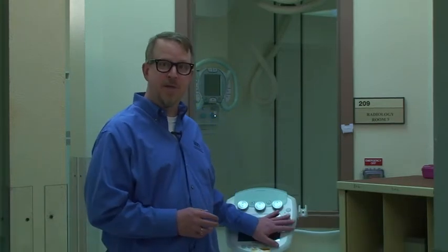The control panel for the X-ray tube contains exposure controls and an exposure button that can be connected by a cord so that the technologist can hold it in his or her hand. The cord should not be long enough to allow the technologist to enter the imaging room while making an exposure. For the safety of both the technologist and the patient, there should be a leaded glass window that allows the technologist to watch the patient without being exposed to radiation.